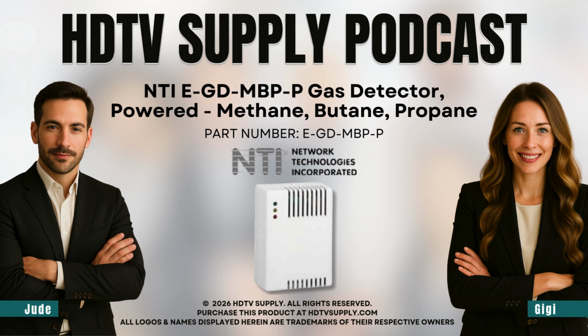And the electrical output seems just as versatile. It is. The relays are level selectable, so you can configure the output as normally open or normally closed. And it can handle a decent load? A very decent load. Yeah. It's rated for a max of 5 amps at 250 volts AC. That means it can interface with pretty much any control panel out there, even older systems that need more power for switching. So it's ideal for retrofitting.